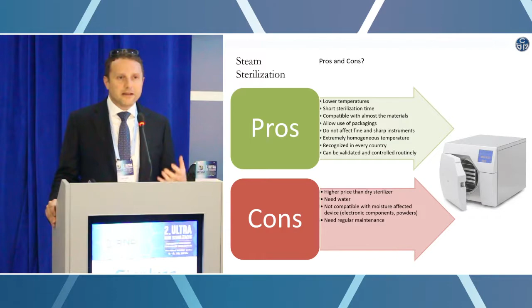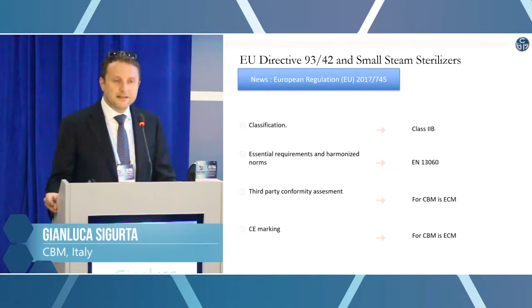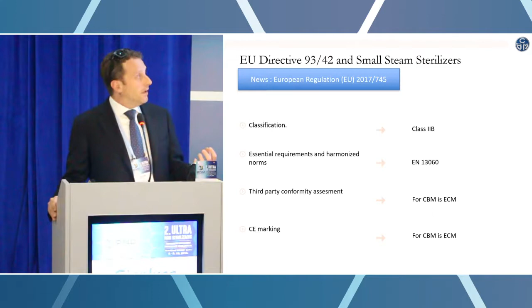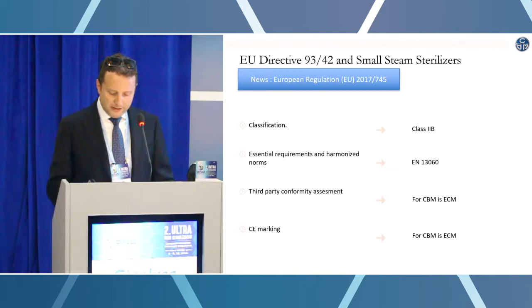So from the normative point of view, what can we say about the small steam sterilizers? In Europe, they fall under the European Directive 93/42, which is now more or less dying, let's say, because a new regulation on medical devices will supersede the European Directive in May 2020. The steam sterilizers are classified as Class 2B, differently from the big sterilizers that you may have in your CSSD. The reference norm is not the EN 285, but the EN 13060, which is dedicated exactly to the small benchtop steam sterilizer.